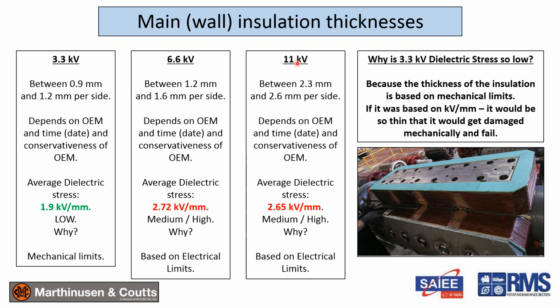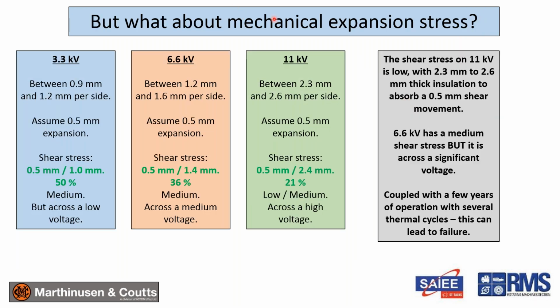But the reason the 11 kV is so is because it's based on electrical limits, same as the 6.6. The 3.3 is a lot lower because if you based it on the electrical stress, it would be so thin that it would experience mechanical failures. So that's why 3.3 is a lot lower, and that's quite relevant to the question posed in this presentation. So now let's look at the mechanical expansion stress on three example stator half coils of 1 meter in length. If we assume 0.5 millimeter expansion, so there I've taken that 1 millimeter and I've assumed that the coil expands from the center of the core, which may not necessarily be true, by the way. It often expands from either end. Then the shear stress is 0.5 millimeter over 1 millimeter of insulation.